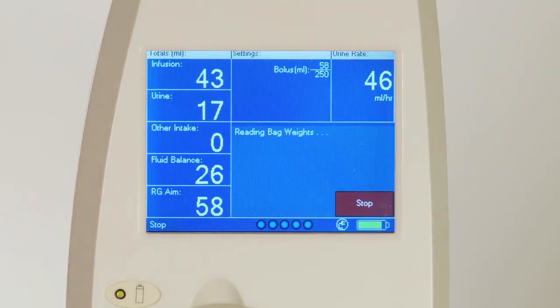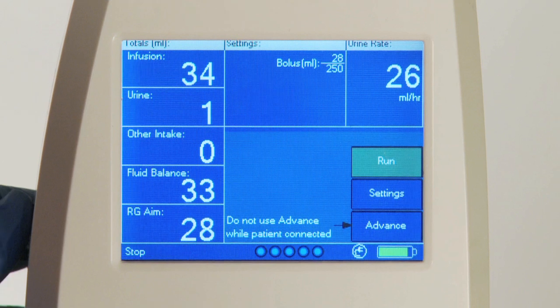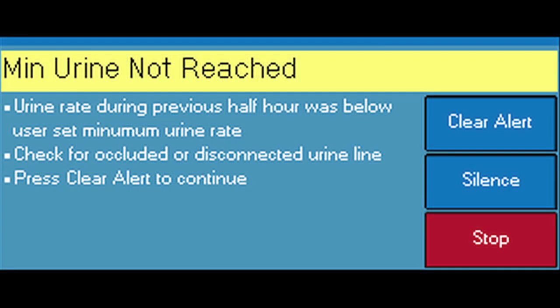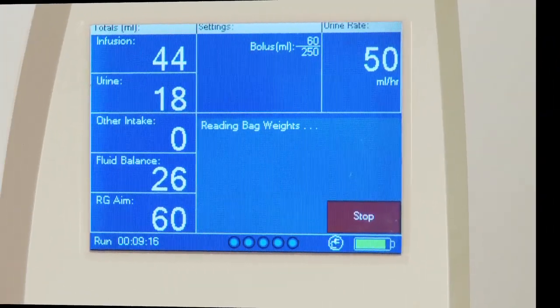Press Run to resume therapy. The default minimum urine rate is 150 milliliters per hour. If the urine output is consistently below the set level for 30 minutes, an alert will sound and the following message will be displayed. Note that it is very common for this alert to occur during the beginning of RenalGuard therapy, prior to the administration of a diuretic.